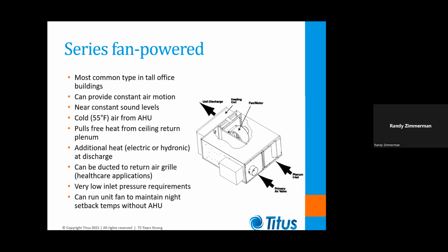It's also important to show that you can duct that induction port back to a return air grill in the room if you need to. You do need to try to keep the pressure drop on that ductwork as low as possible. And of course, in healthcare applications where you're not allowed to share return air between two spaces, you are required to duct that induction port back to the patient room.